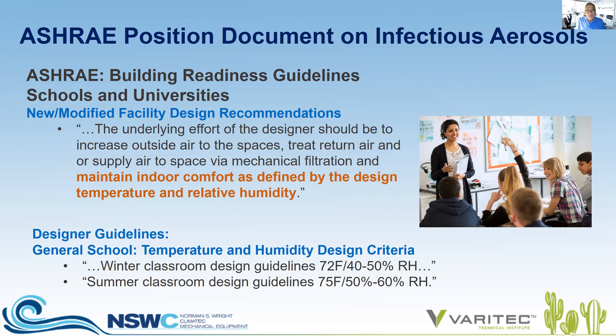The ASHRAE Epidemic Task Force website building readiness guidelines state, regarding schools and universities, that the underlying effort of designers should be to increase outside air to the spaces, treat return air via mechanical filtration, and maintain indoor comfort as defined by design temperature and relative humidity. Under general school guidelines, temperature and humidity in winter should be set at 72 degrees dry bulb and a humidity range of 40 to 50%. In summer classroom design, room set points should be in the range of about 75 degrees Fahrenheit and 50 to 60% RH.